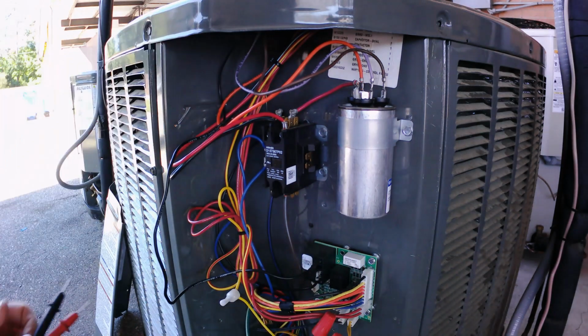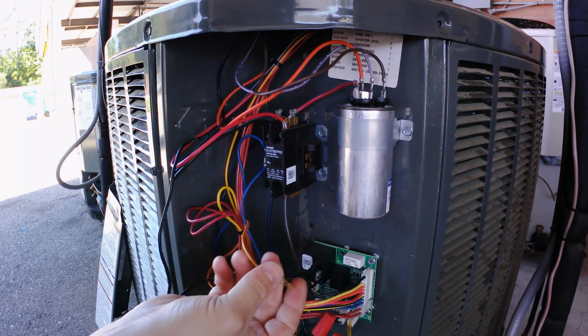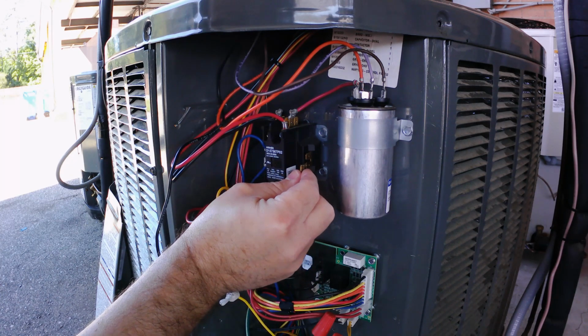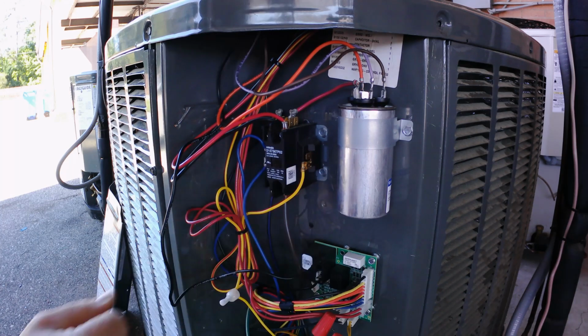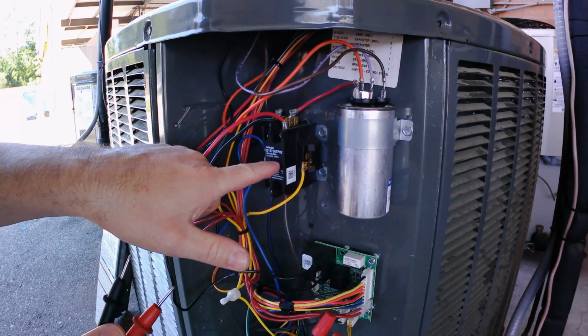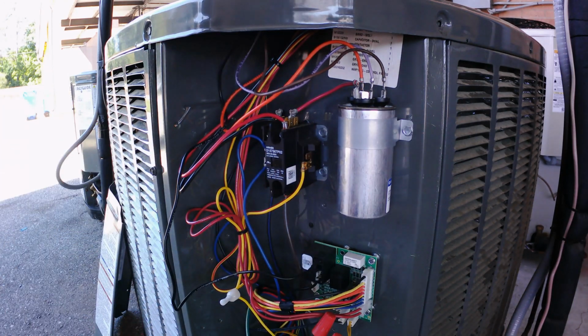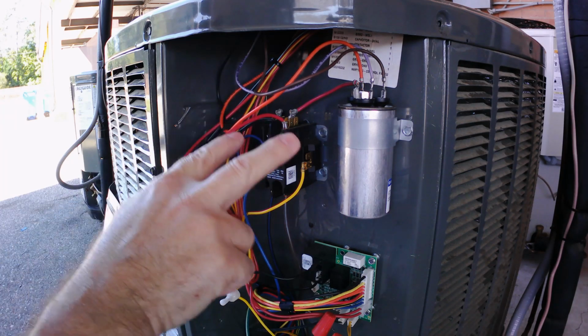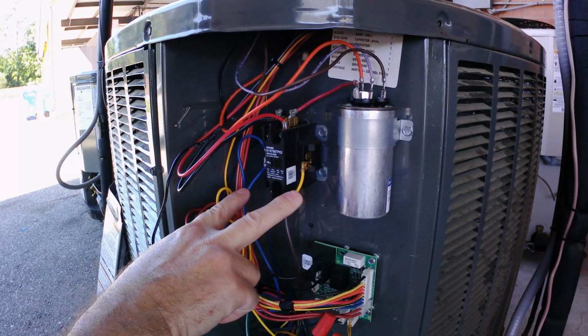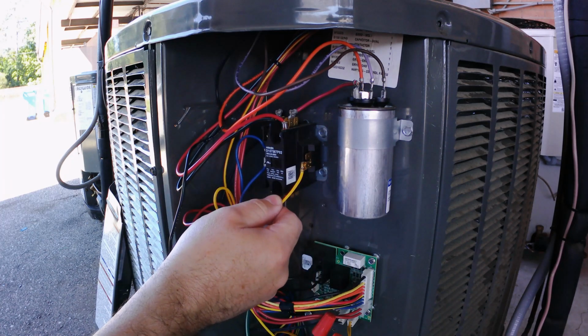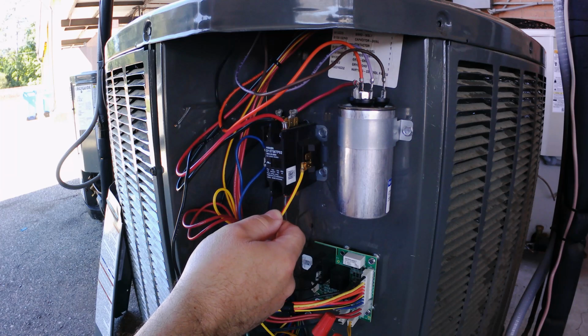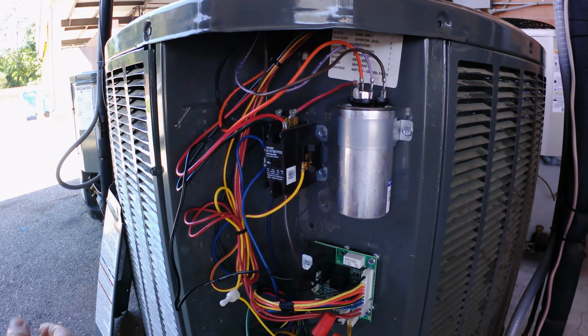So I can safely say in my head that, hey, if this coil were to get powered, then it should move the switch. A lot of guys are going out here and they're pushing their finger on the contactor switch. That's not the way this is intended to work. So use your meter. If you have 24 volts, then the next thing I want to do is remove the low voltage wire on at least one side and ohm out the coil. You may not have a good coil there.